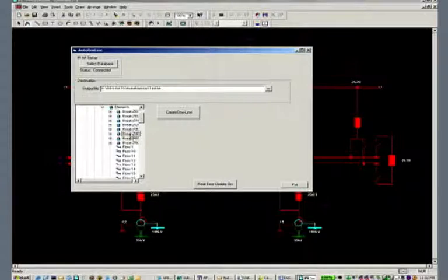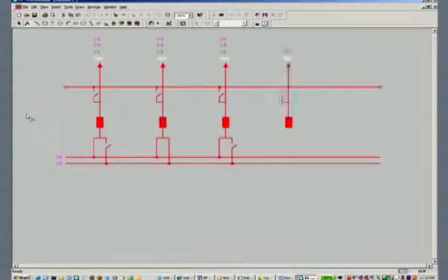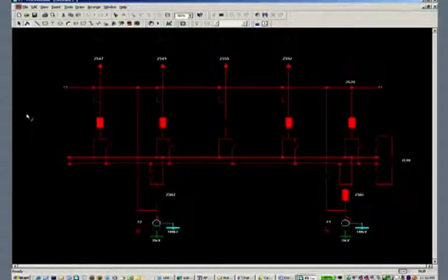expected. Now we will create our one-line display in real-time demonstration mode. The tool will only draw what it can recognize as valid components of a model. It will perform a best fit of the drawing elements in Process Book based on the customized logical design model of the substation. You can see here that the new model is drawn without the breaker we deleted.